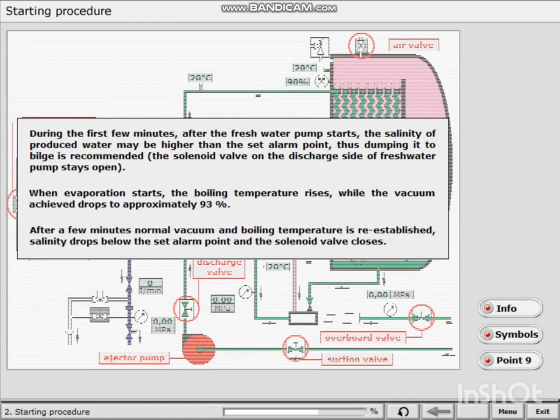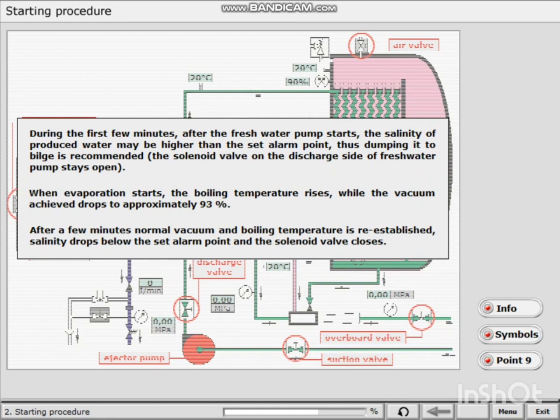During the first few minutes after the fresh water pump starts, the salinity of produced water may be higher than the set alarm point, thus dumping it to bilge is recommended.